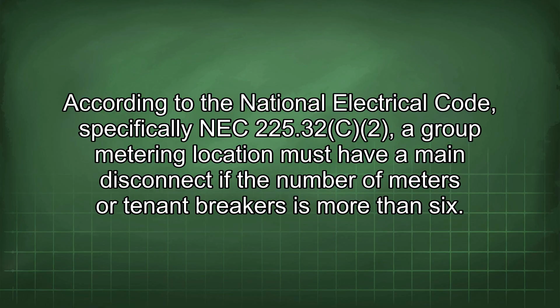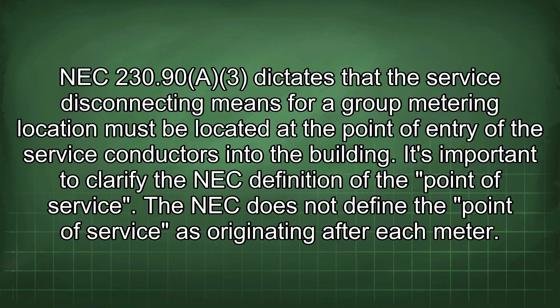It's important to clarify the NEC definition of the point of service. The NEC does not define the point of service as originating after each meter. The NEC defines the point of service as the point of entry of the service conductors into the building. This means that the disconnecting means applies to the feeder from the transformer to the main terminal box of the group metering. Given these requirements, a group metering location with more than 6 meters or tenant breakers necessitates a main disconnecting means at the point of entry of the service conductors into the building.